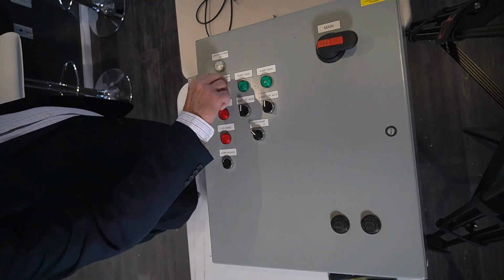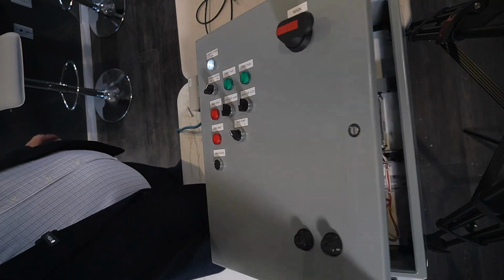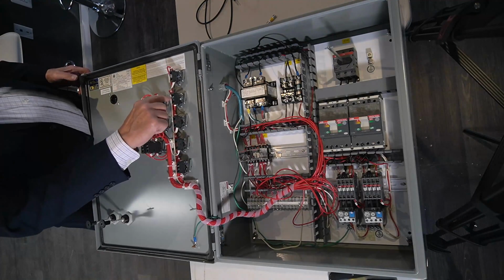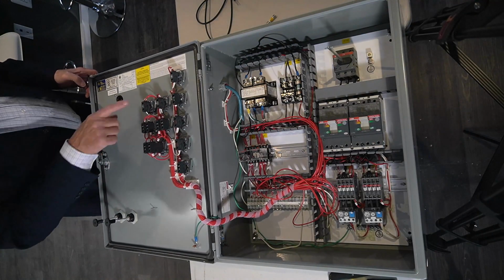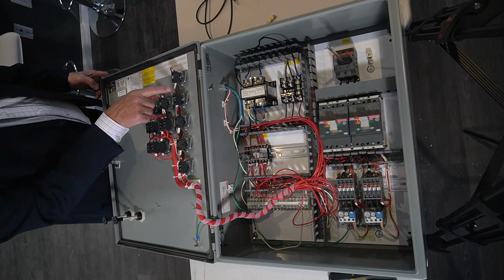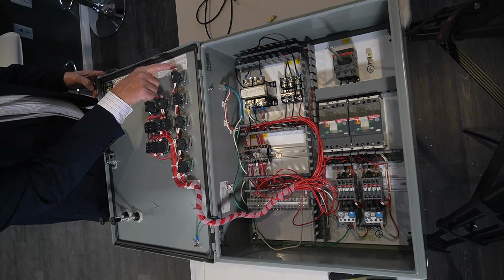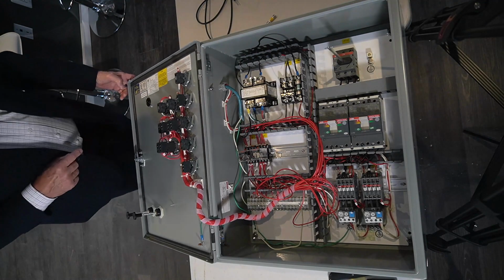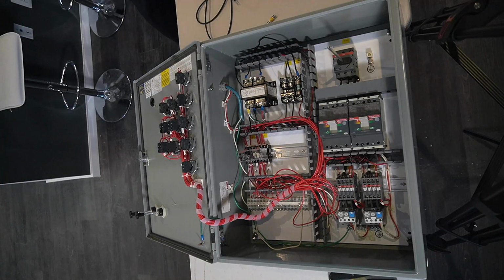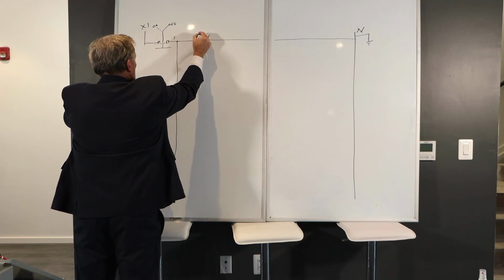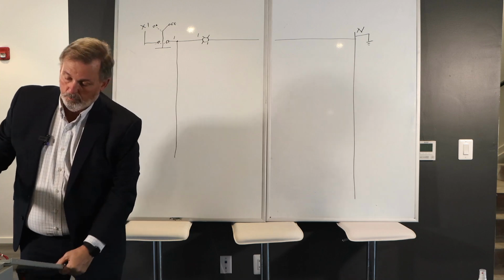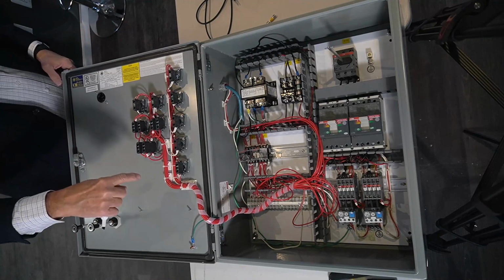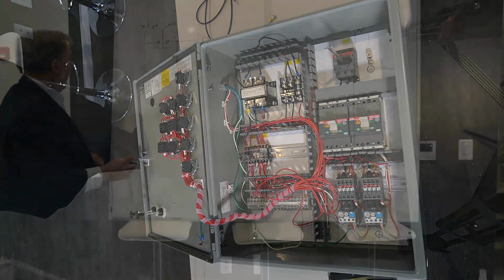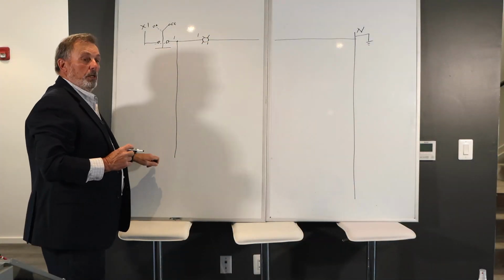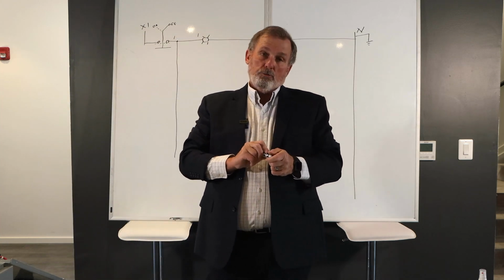Looking at the outside of the cabinet, we've got a power switch on and off. Inside the cabinet, what that looks like is this switch right here is turning this light on. On the X2 side, I've got the neutral right here, and wire number 1 comes off of this switch. So I'm going to stay consistent with the wiring in the cabinet. This is going to be my number 1. And if you notice, 1 goes to the light and then comes off the light and back into the control cabinet. So that's why I've got this rung here. This number 1 is going to be my input power to all of my inputs, outputs, and so forth.